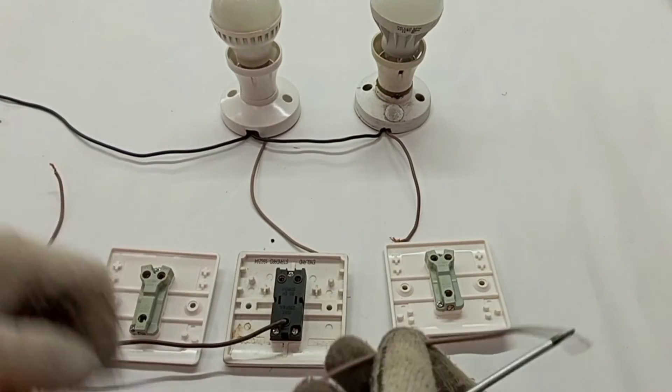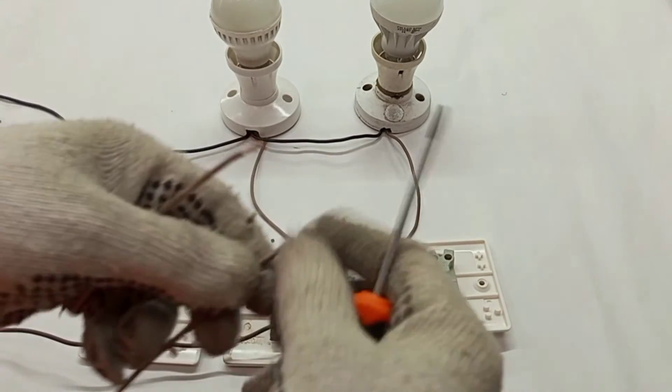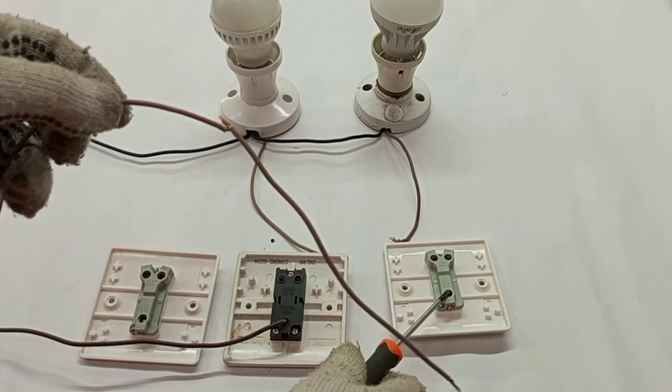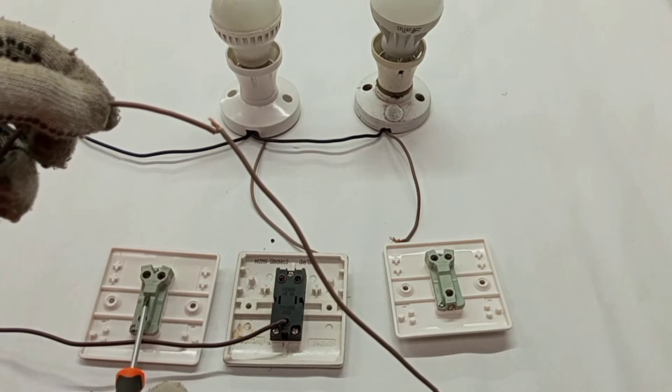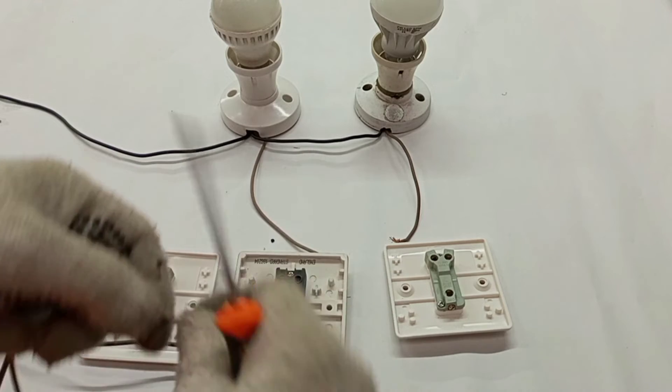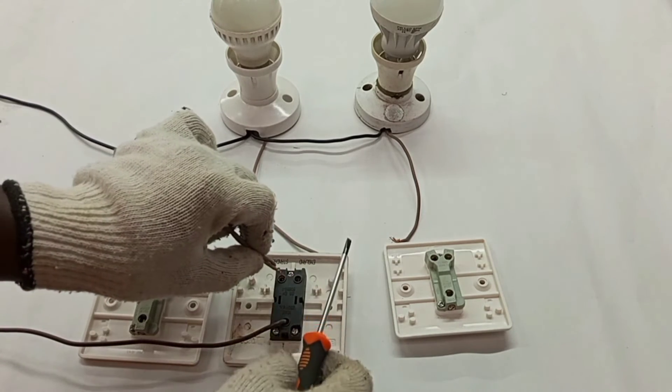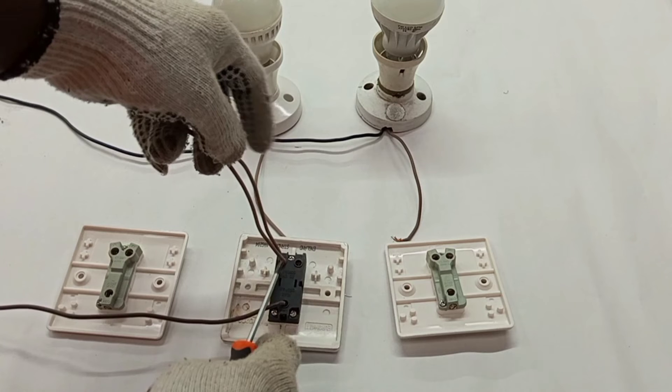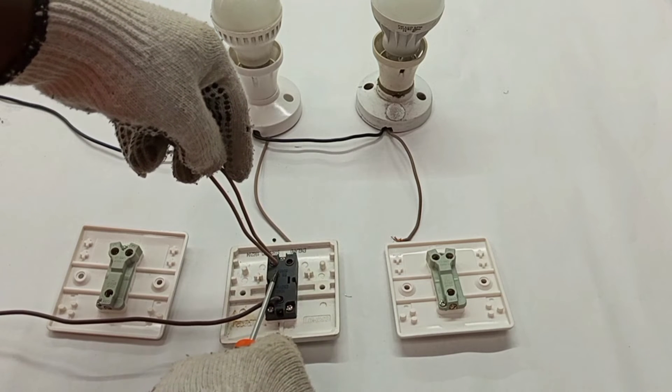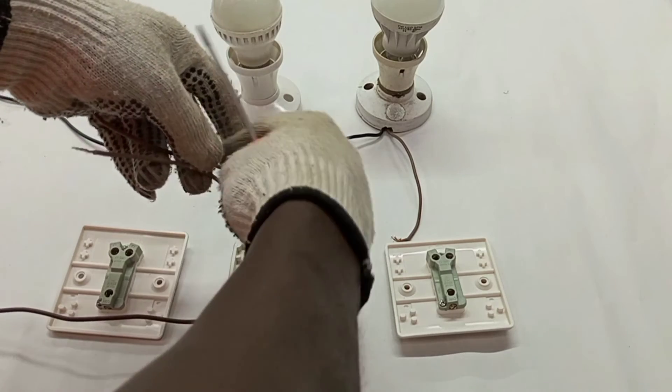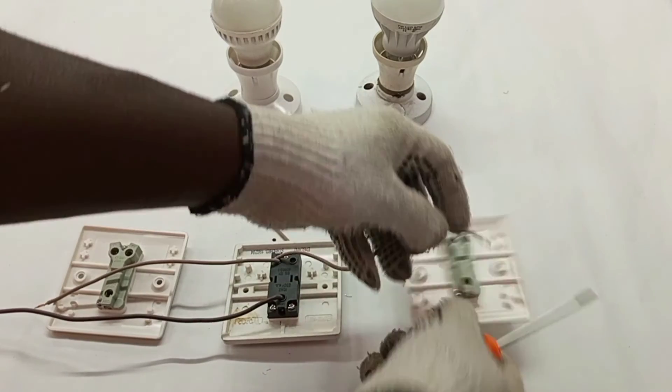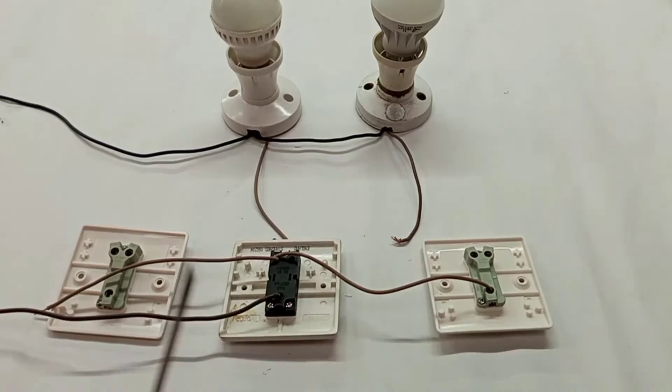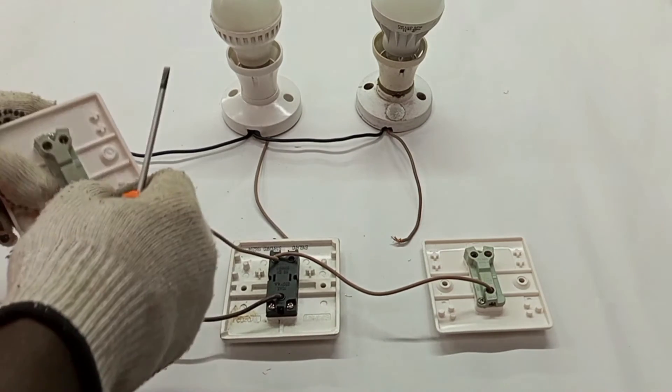I would need two cables. What am I doing with those two cables? I'll join them together, and so these cables now will serve as supply cables to this switch and then this one. I'm taking it from L2 of the master switch. So we have feed here, and then I have two wires connected from the L2 terminal of the master switch. One of those will go to the common of this switch, and then the other one will go to the common here.